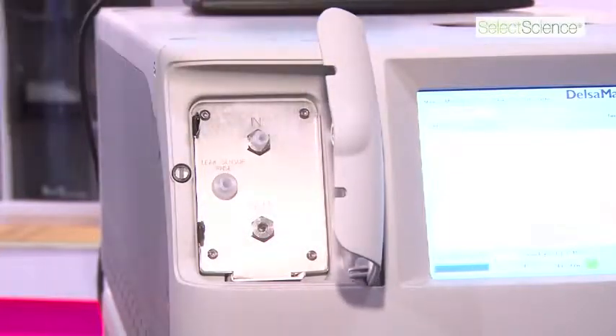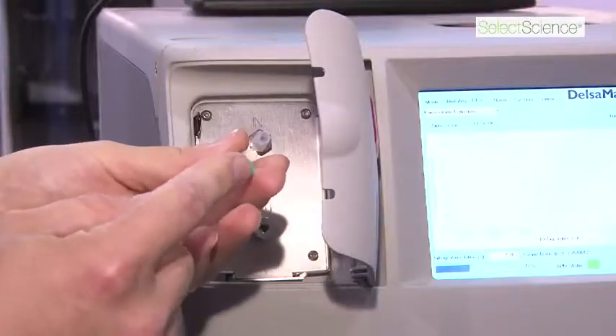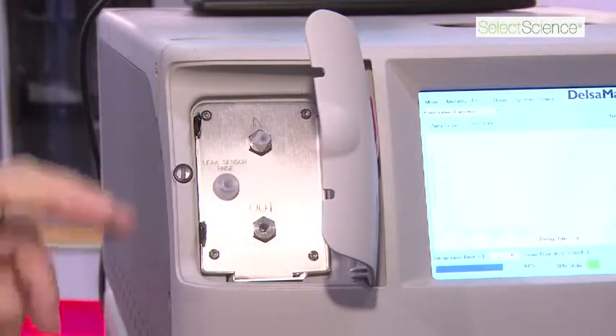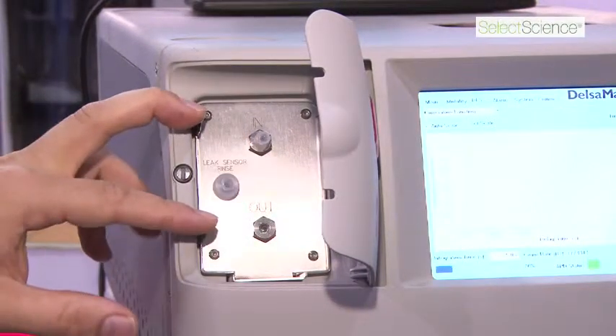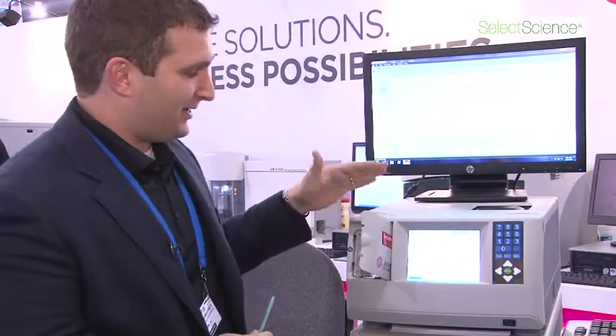The sample injection is very simple. I take a syringe, I can inject it right here into the in port and the waste will come out the output, or you can recollect the sample. That means that you don't have to fumble with complex cuvettes — there are no disposable cuvettes. It's very simple to clean the system.